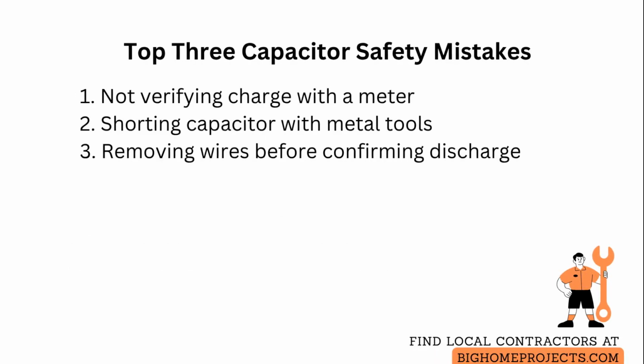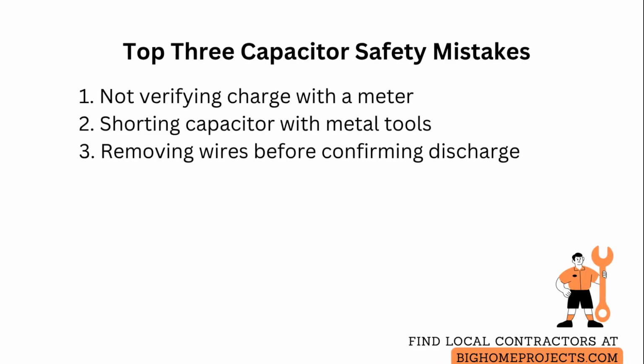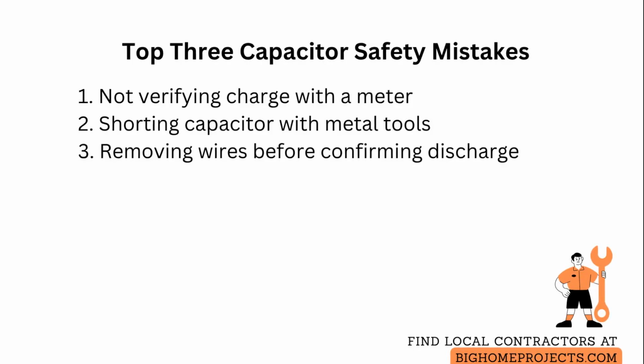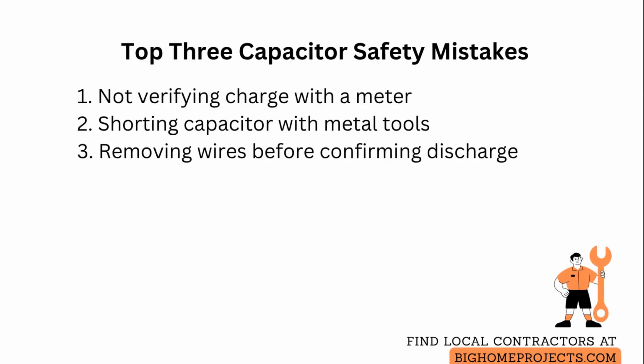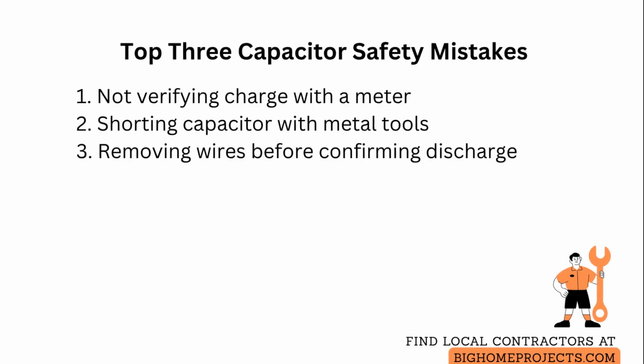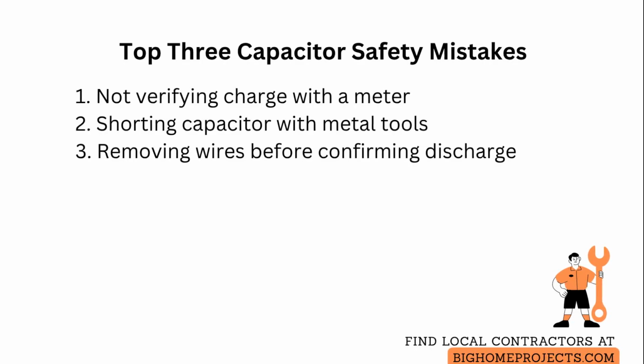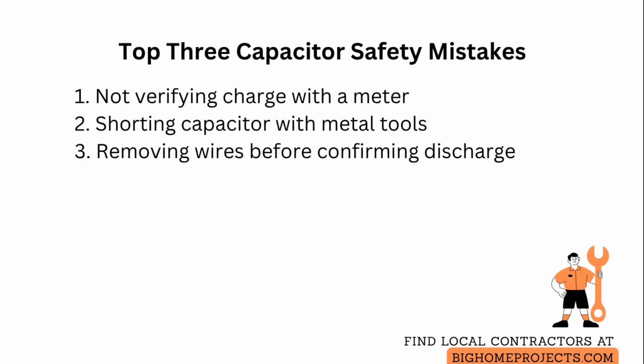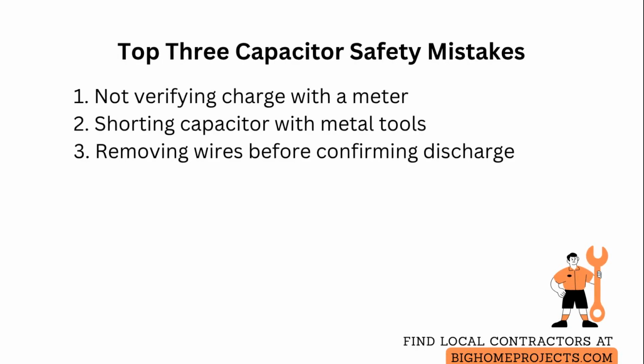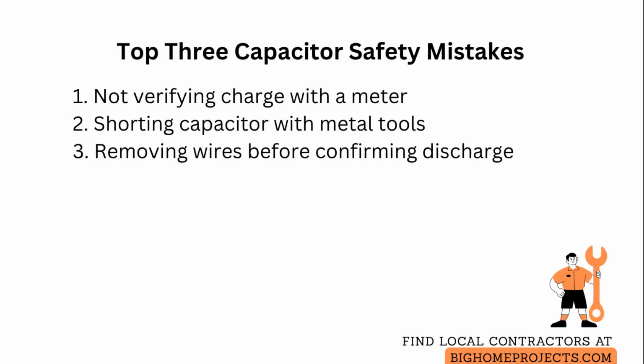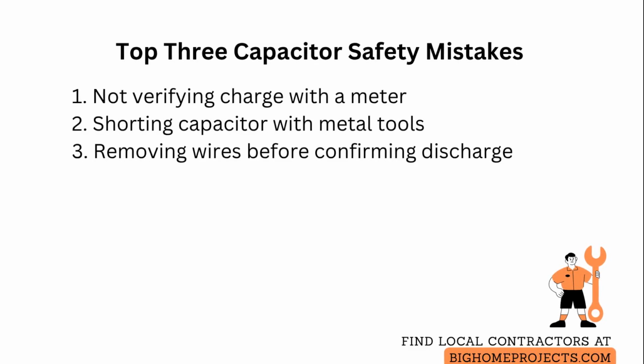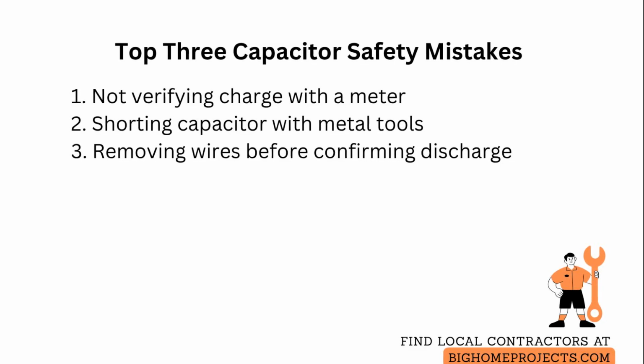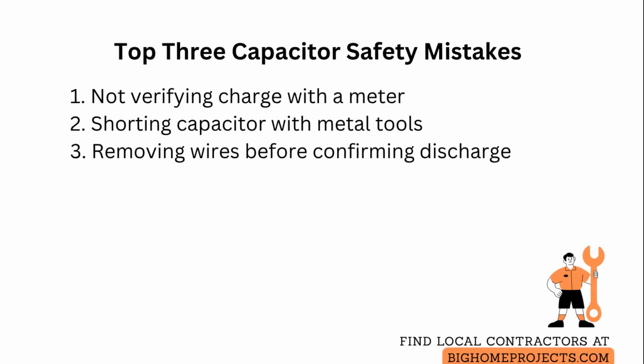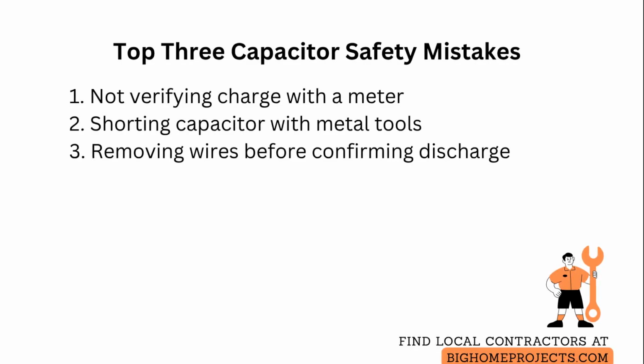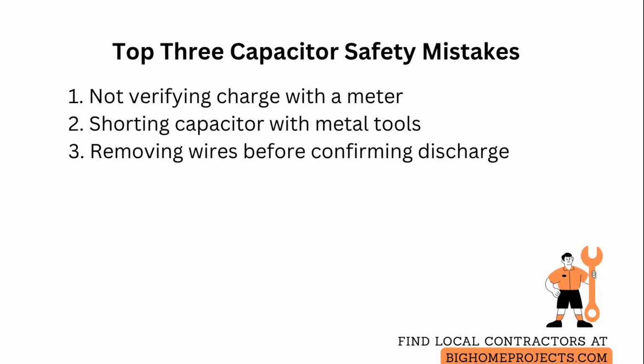Common mistakes include relying on the disconnect alone without verifying with a meter, which can leave a dangerous residual charge, so always test across terminals before touching and after attempting a discharge. Another error is shorting the capacitor with a metal tool, which produces sparks and can rupture the capacitor, so use a resistor-based discharge method or the meter discharge feature instead. A third issue is removing wires before confirming the capacitor is drained, which risks shock. So always discharge and then confirm a near 0 voltage reading before using insulated pliers to remove wires.